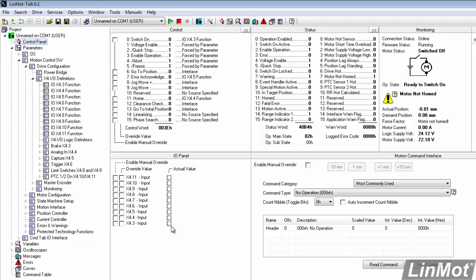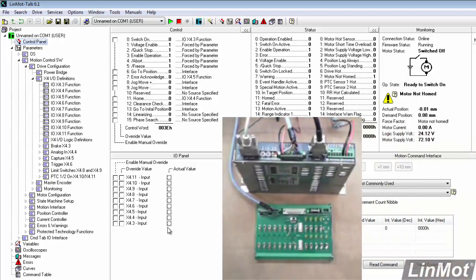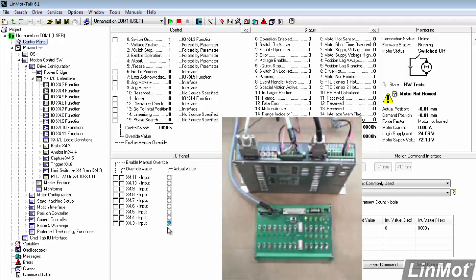So, this allows us to confirm that our bits are actually being read. My X4 pin 3 was configured as the switch-on bit. So, I can reach in here, I can switch that bit, and you'll notice that we get an indication here that that bit is true. And now, up here, our switch-on bit is true. And over here, it says operation enabled, motor not home.